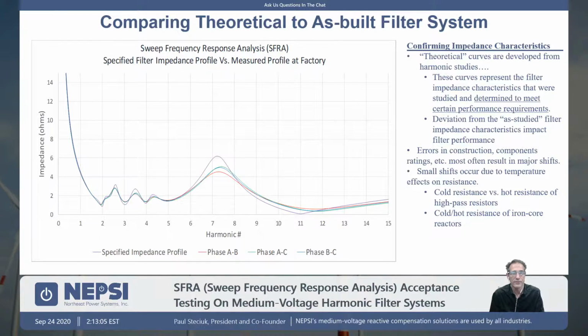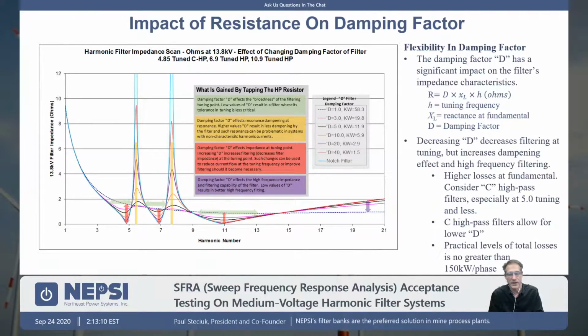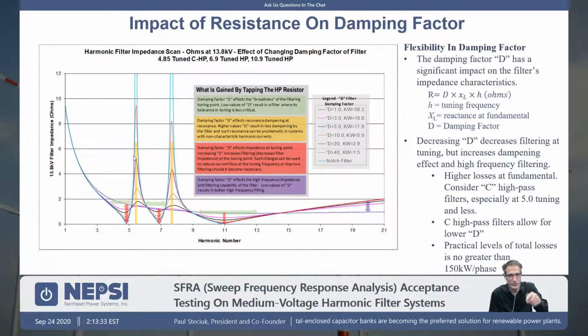So we're talking about some things that we might catch. If I go to the next slide here, if I have a resistance change, values of resistance within the filter itself, you can see what happens as we change the resistance of the circuit here. These are just the high-pass resistance values that we're changing. We get a different shape in the impedance curve. So differences in the resistance of the high-pass resistors result in a different shape in the impedance curve. So this is one thing that this device will capture. It will capture that impedance profile and the impact of resistance on the system.